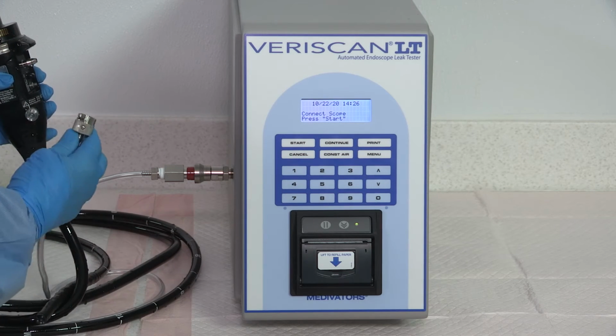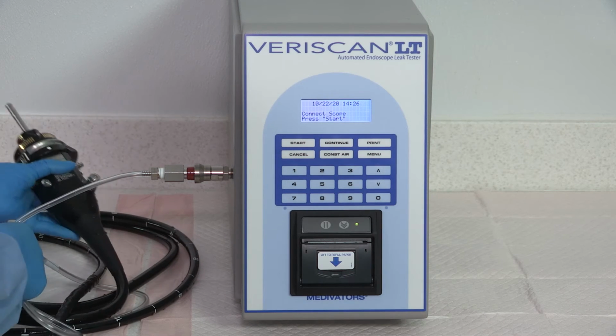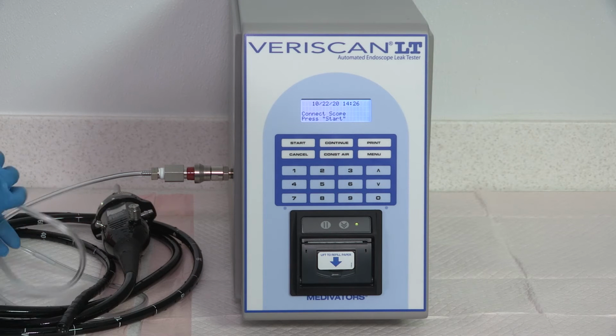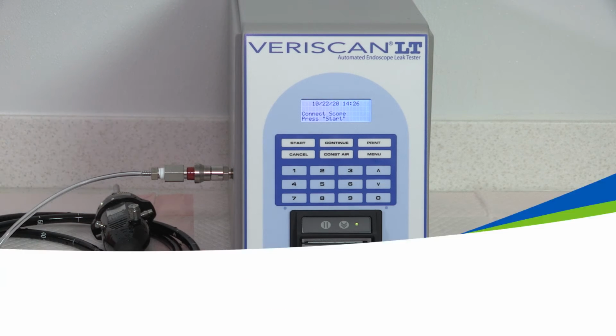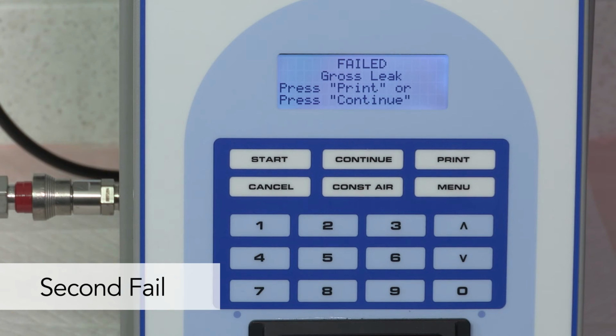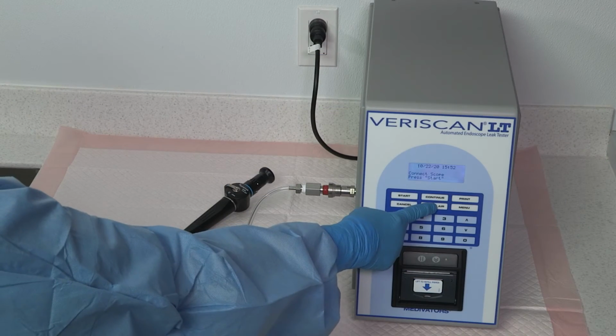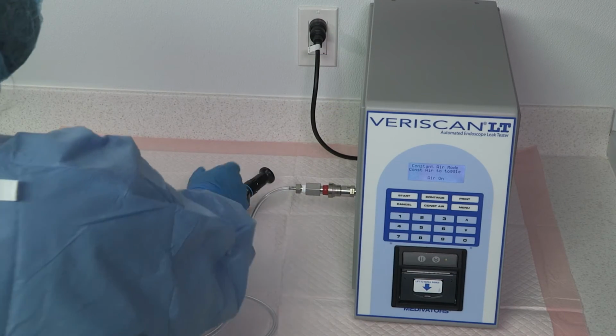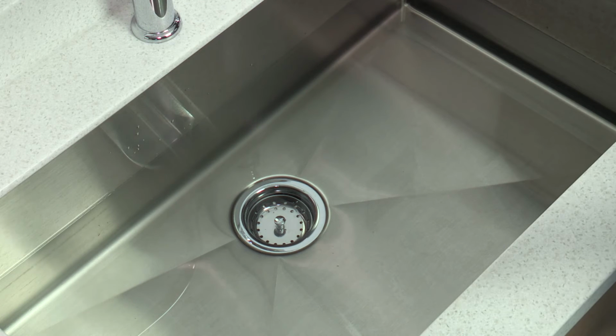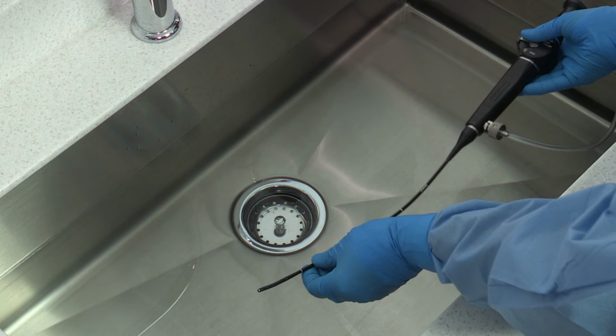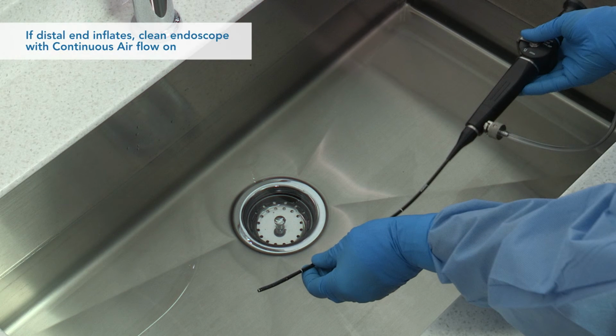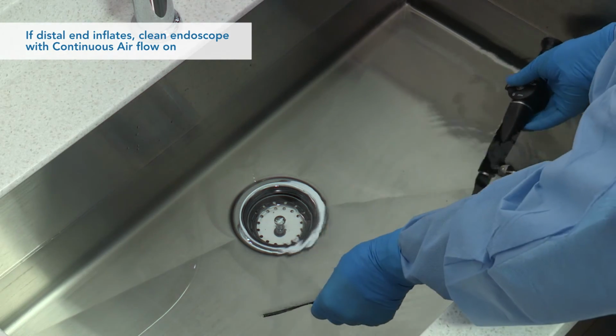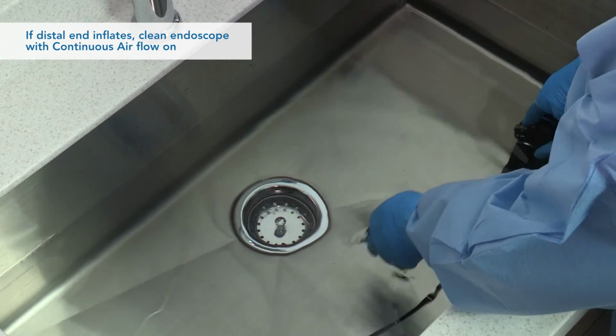Disconnect the Quick Connect tubing from the endoscope. The endoscope is now ready for the next step in the manual cleaning process. If an endoscope fails a second time, press the constant air button on the keypad. Visually observe the endoscope's distal end for inflation. If the distal end of the endoscope inflates, then it can be safely submerged in clean water without detergent.